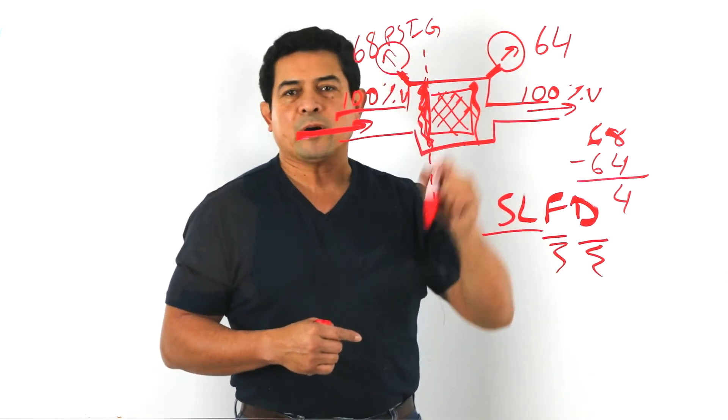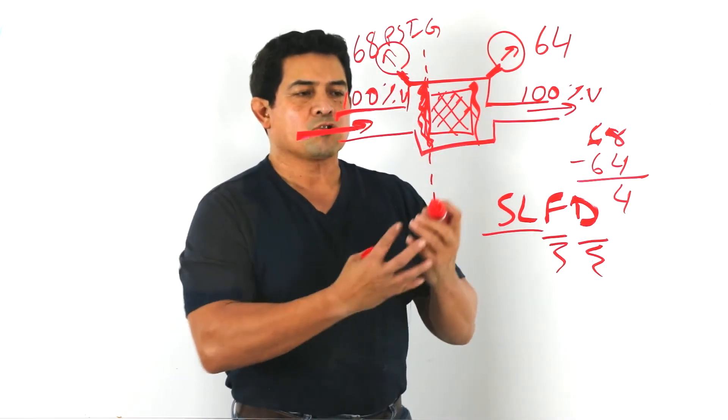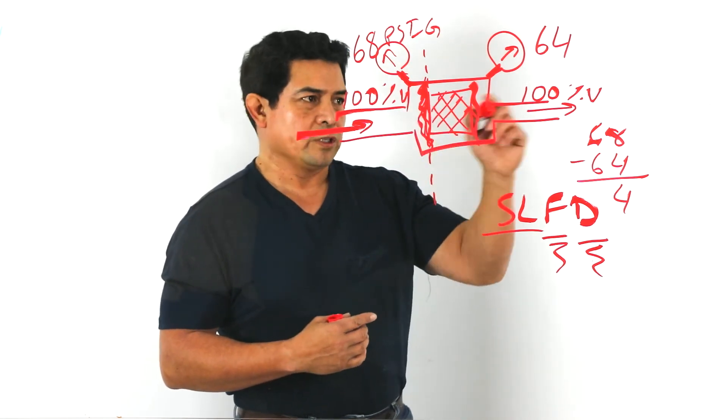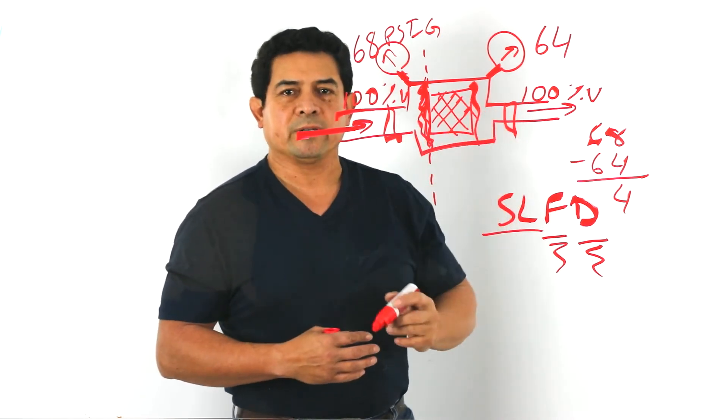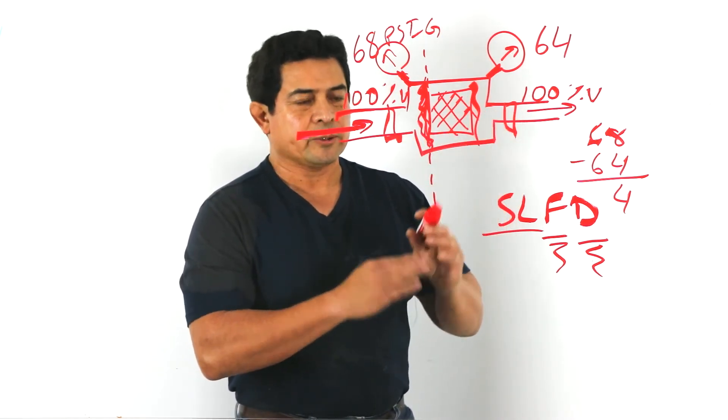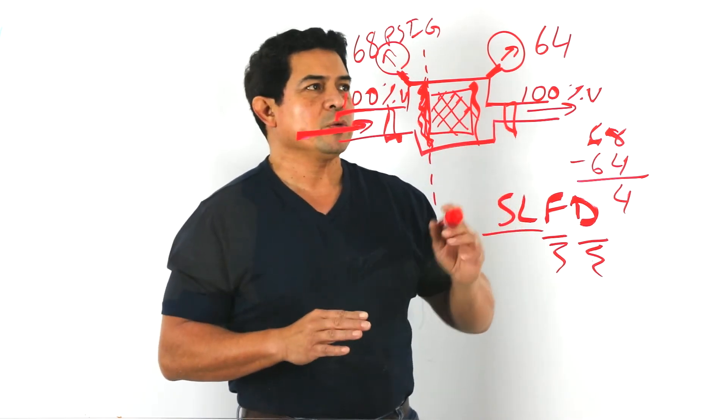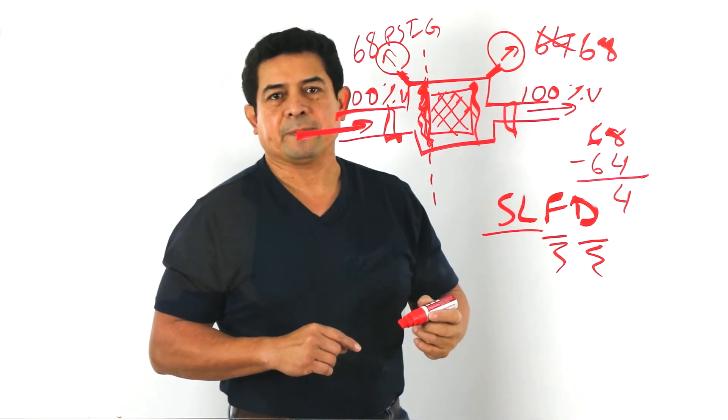Because we have the pressure difference, we know that this dryer is bad. This dryer needs to be replaced. So now what we can do is just cut the dryer out and put a new one in. There's more to it than just that, but we need to replace this and put a new one in. Once we put a new one in, we're going to notice that now both pressures will be the same.